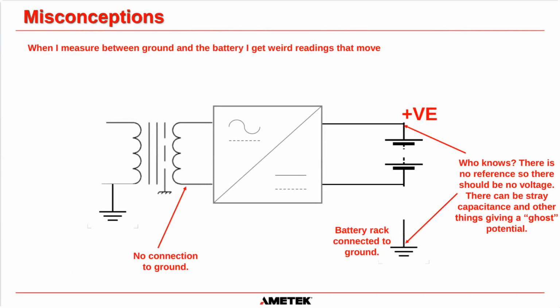Okay. The next one is when I measure between ground and the battery, I get a weird reading. What do I do? Remember, the important thing about that weird reading is, is it steady or is it tending to move towards 0 volts? Okay. If it's steady and it's not the halfway point of the battery, then yes, you probably have a soft ground fault.